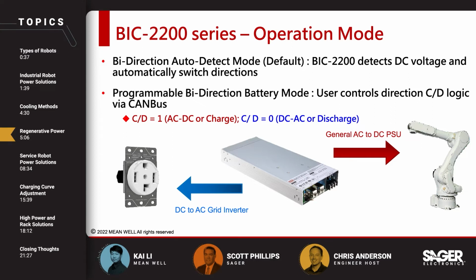And then when the robotic arm is suddenly braking or doing a falling down motion, a sudden high voltage will appear on the BIC-2200 output side because of the motor characteristics, the back EMF. And the BIC-2200 will be able to switch quickly into the regenerative mode, which is the DC to AC mode, and then dissipate that force back into the AC grid.